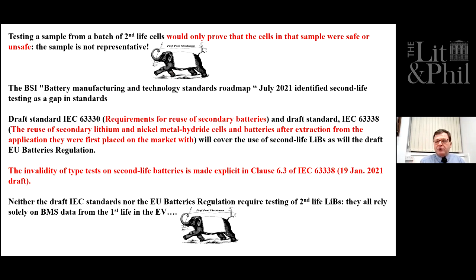Type tests will only prove that the modules or cells tested are safe or unsafe. It's not representative - elephant in the room. The BSI has identified that tests for second life batteries is a major gap. The draft standards IEC 63330 and IEC 63338, which will be adopted by Britain and other countries, are supposed to cover second life batteries.